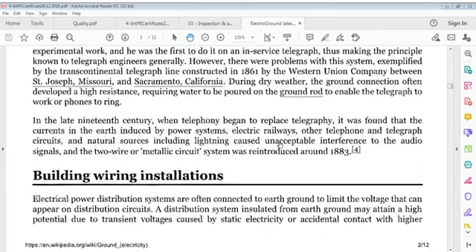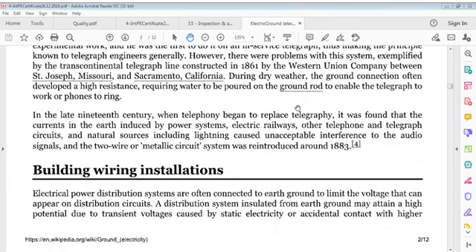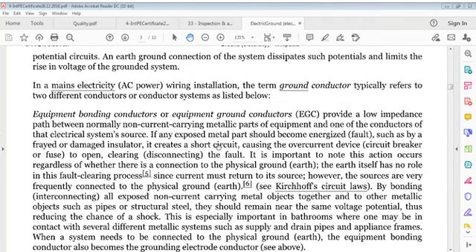I read again, it's also technical. Electric power distribution systems in our homes or elsewhere are often connected to earth ground to limit voltage that can appear on distribution circuits, meaning on our distribution board. A distribution system insulated from earth, insulated meaning it is not connected to earth, may attain a high potential if there is no earthing. That is, it may attain a high potential due to transient voltages caused by static electricity or accidental contact with higher potential circuits. An earth ground connection of the system dissipates such potentials and limits the rise in voltage of the grounded system.